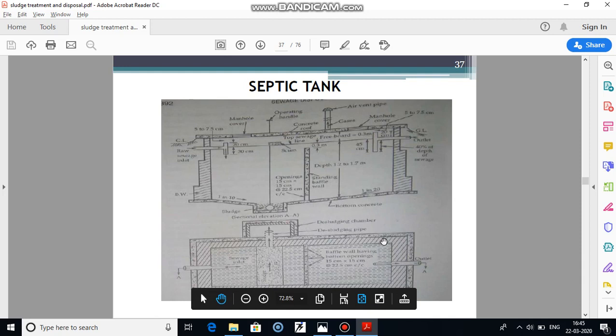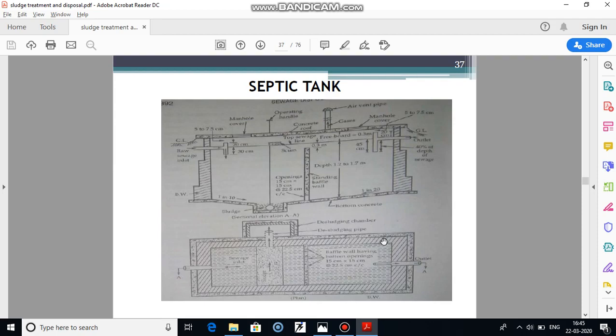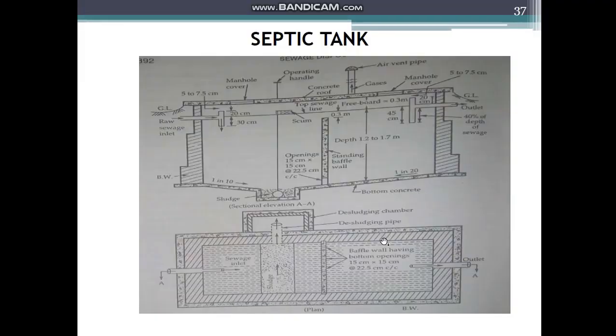Going to the construction details: the tank is designed to prevent direct currents between the inlet and the outlet, ensuring effective sedimentation. This is achieved by using T-shaped pipes, so there is no direct entry of sewage into the septic tank. T-shaped pipes are provided with submerged ends at both inlet and outlet.